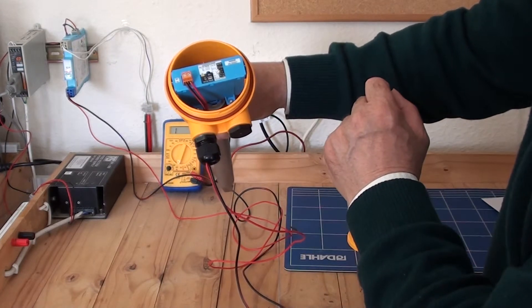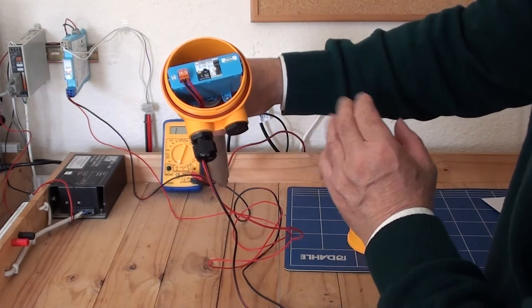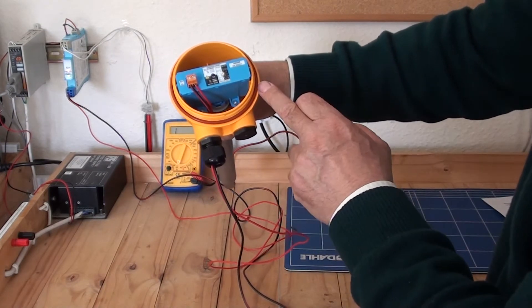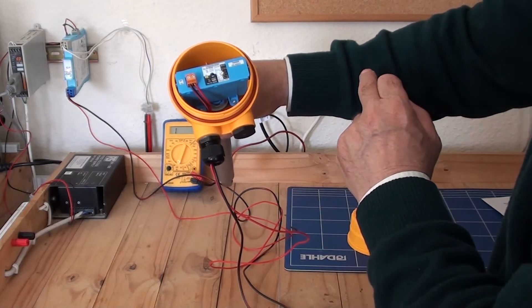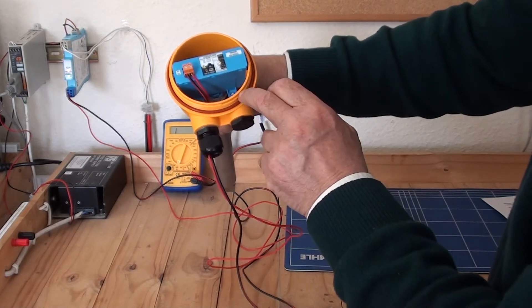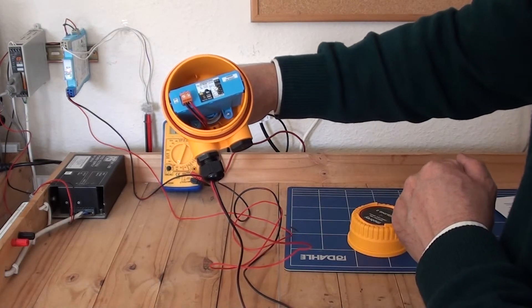On the cassette I have an operation mode where I can select if the output is to switch when it is dry or wet. I can also set the delay time from 0.3 up to 3 seconds to allow for any ripples or turbulence in the tank.